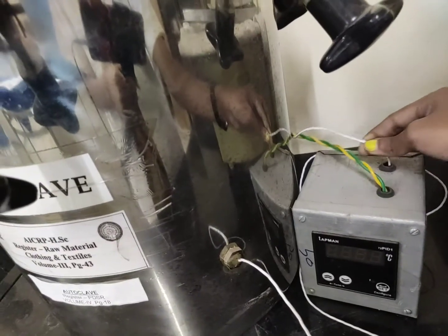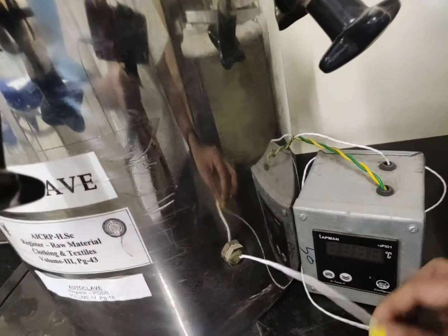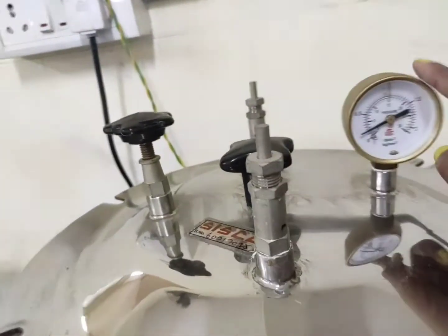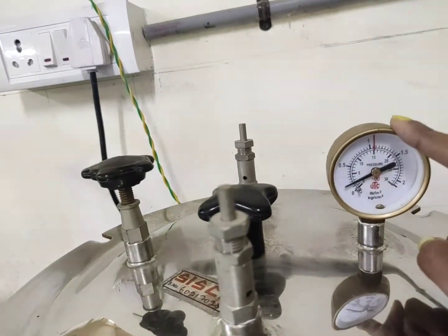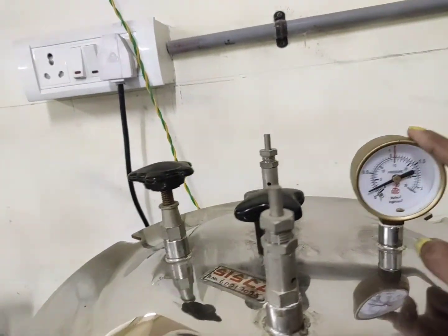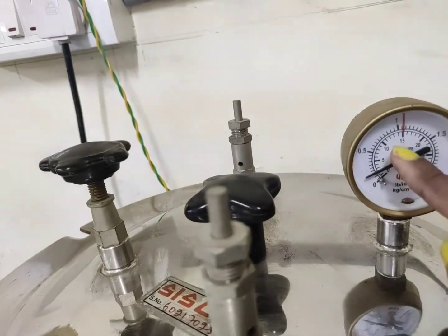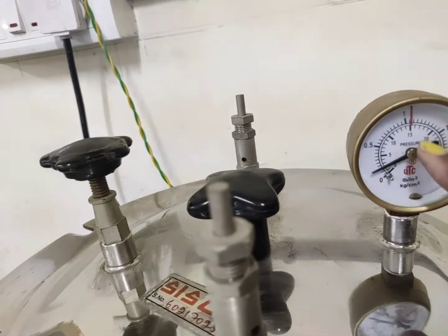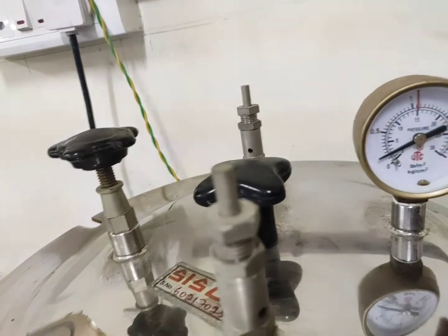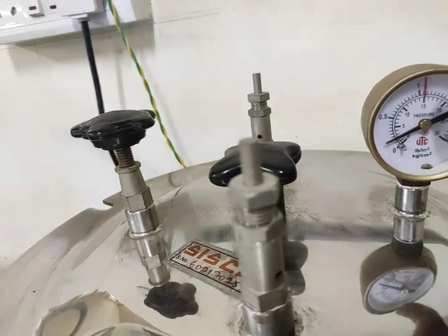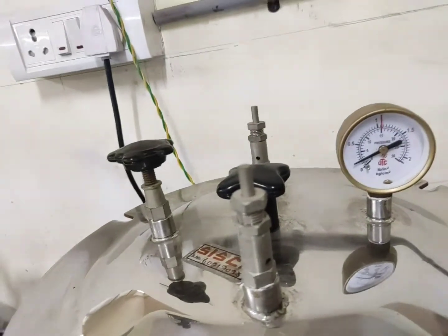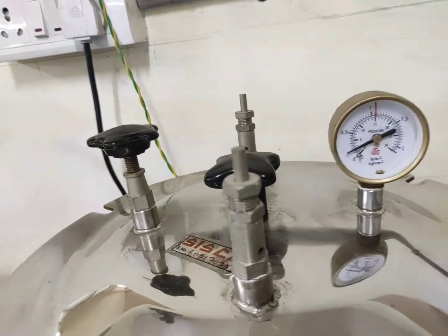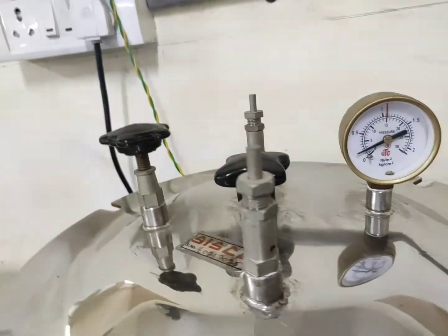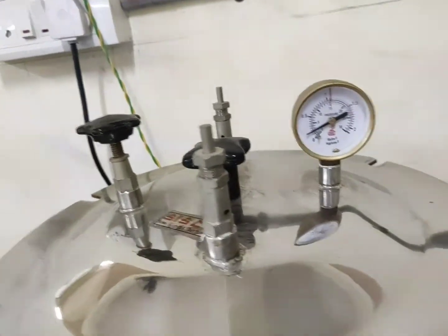Okay, that is possible because of this white wire which is attached to the sensor that is present inside the autoclave. Okay, that is one thing. Next thing is, as I was talking about this pressure gauge, it will show you exactly how much pressure has been built inside. Now I have mentioned that the pressure that you need for autoclaving is around 15 psi, that is pounds per square inch. Okay, so once it reaches 15, that means the pressure has been reached, and at the same time at that pressure you will see 121 degrees centigrade in case your autoclave is working perfectly. So both are coordinated.